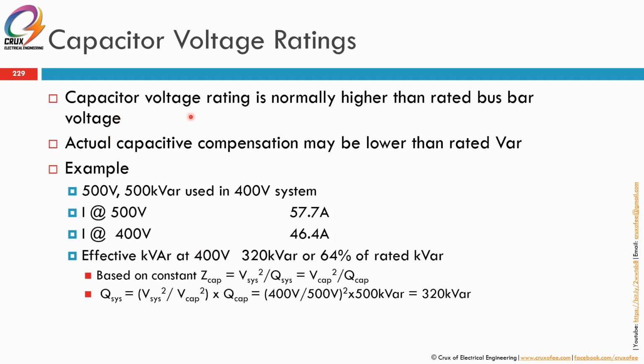Capacitor voltage rating is normally higher than the rated busbar voltage, so the actual capacitive compensation may be lower than the rated VAR. This is not really related to protection, but just for knowledge. For example, if the rating of your capacitor is 500 volts, 500 kVAR, used in a 400 volt system: at a 500 volt system you get exactly 500 kVAR, but at a 400 volt system the effective kVAR is only 320 kVAR. This is the typical rough calculation to estimate the actual VAR depending on the voltage used.